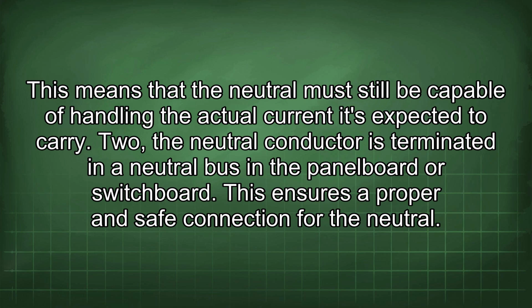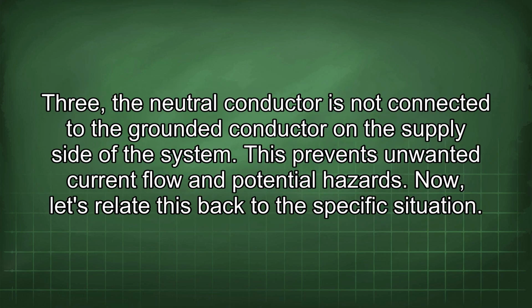2. The neutral conductor is terminated in a neutral bus in the panelboard or switchboard. This ensures a proper and safe connection for the neutral. 3. The neutral conductor is not connected to the grounded conductor on the supply side of the system. This prevents unwanted current flow and potential hazards. Now, let's relate this back to this specific situation.